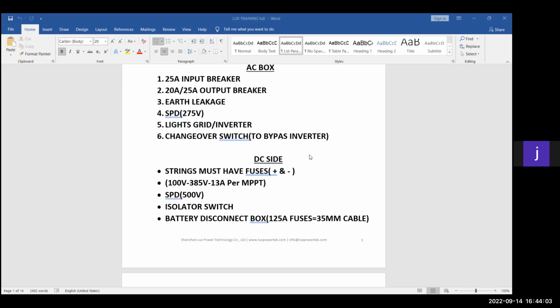But as long as it's just higher than 13, it's fine, but not much higher than, let's say, 13.1 to 13.2 max that you can use before you will get into trouble. So we have a 480 volt maximum. On the voltage side, what you see here is my operating range. That is the range within which an inverter is the happiest on the MPPT side to work. So the MPPTs will be the most efficient if you keep it between, let's say, 120 to 385 volts. That's where your MPPTs will give you the highest efficiency.